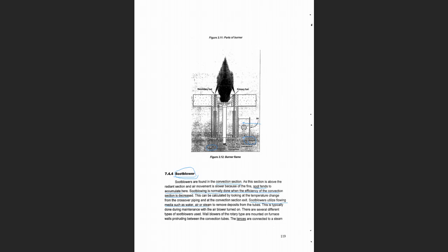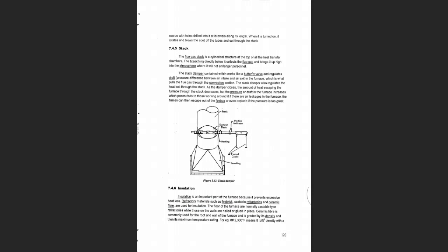Usually they use steam to remove deposits from the tubes. فعادة يكون في connections to the inlet of the convection section from the side من الجوانب of steam line. steam pressure عالي وحرارة عالية، هذا الستيم يضرب على الجدار الخارجي للتيوب وبالتالي ينظف ايش؟ ينظف التيوب من اي تراكمات بالذات اللي هو السوت هذا. جميل. ويعني and after visual inspection ان شاء الله you will يعني give the decision that the tubes are very clear.